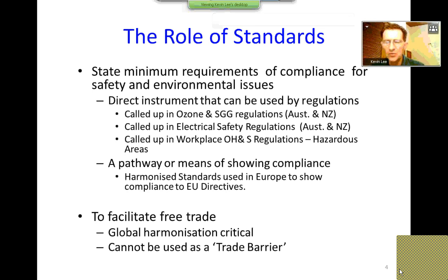As an example, in Australia and New Zealand, we've called up some specific standards in our ozone and synthetic greenhouse gas regulations. We also have standards called up in our electrical safety regulations. This is particularly pertinent when you come to flammable refrigerants and you have the risk of an electrical component igniting any leaked refrigerant. Then we also have standards called up in our workplace and occupational health and safety regulations, and this is for hazardous areas, whether it be a toxic refrigerant or a flammable refrigerant or under very high pressure and there's explosion risk. And in Europe, for example, standards aren't mandatory and they aren't called up exactly in regulations, they are a pathway or a means of showing compliance.